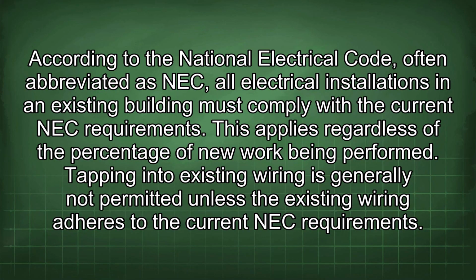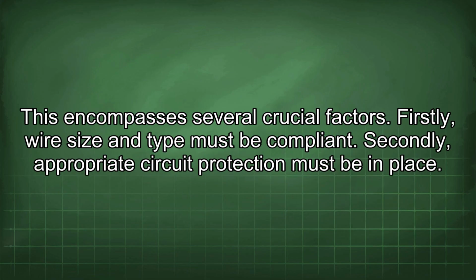According to the National Electrical Code, often abbreviated as NEC, all electrical installations in an existing building must comply with the current NEC requirements. This applies regardless of the percentage of new work being performed. Tapping into existing wiring is generally not permitted unless the existing wiring adheres to the current NEC requirements. This encompasses several crucial factors.